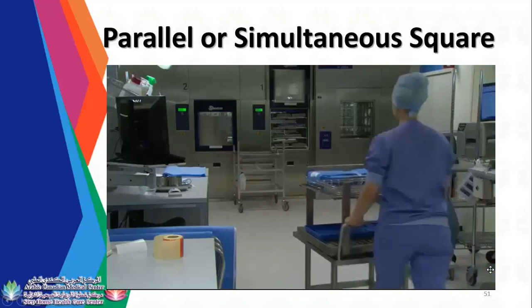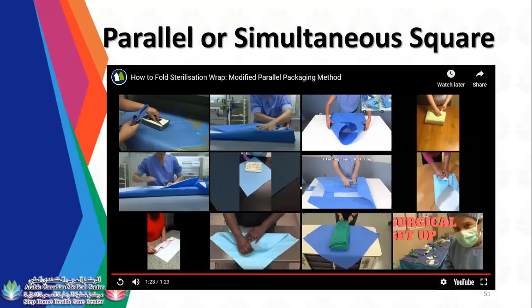Okay, guys, as you can see, when they are placing instruments on the trays, it is properly arranged. The basin or the kidney basin is placed concave face down because it can facilitate the drainage of the steam if ever. It has an indicator tape outside, and it has an instrument label, a set label, whatever the set is intended for. So you need to place a chemical indicator inside, which is class 5 or 6, before covering it or before pouching it.